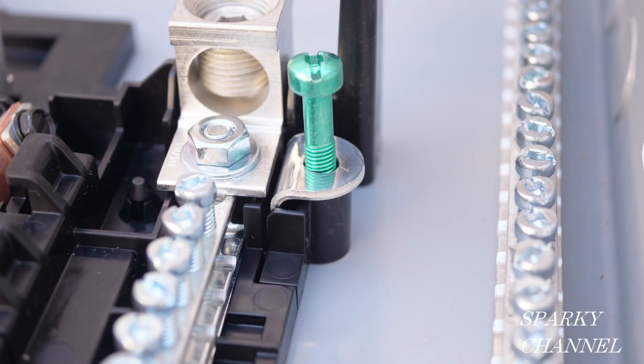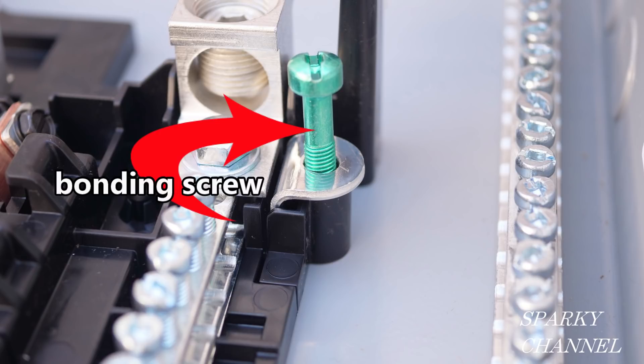So how does this green screw in the Siemens load center relate to the bonding strap in the Murray load center? The green screw is called a bonding screw and it has the same function as the bonding strap, but it's activated in a different way.